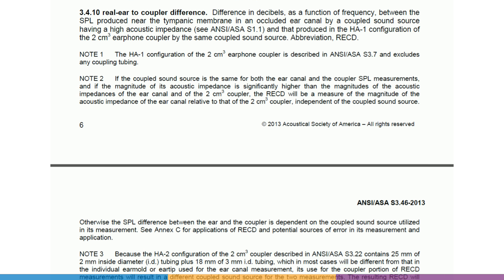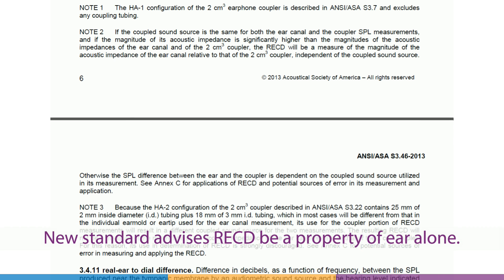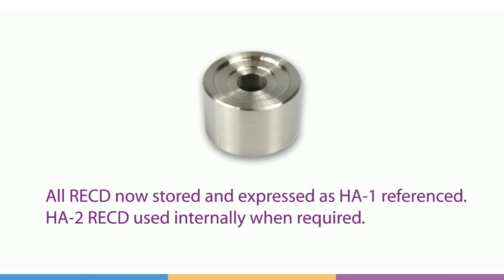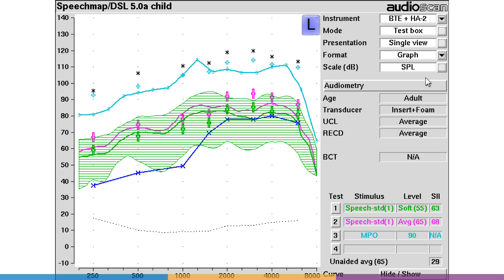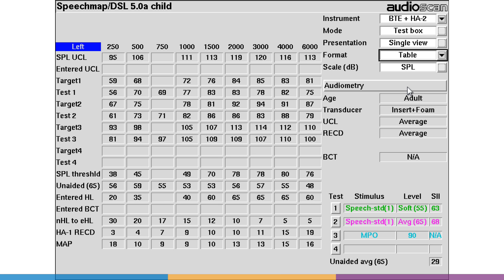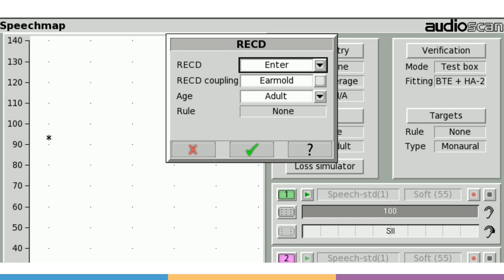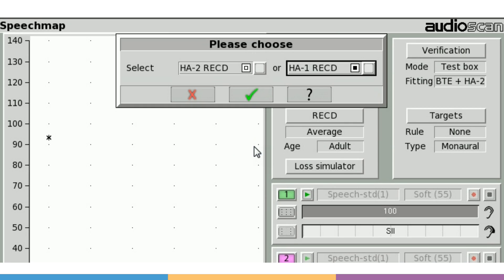The ANSI S3.46-2013 standard advises that the RECD should be a property of the ear alone and not dependent on the sound source and coupling method. To this end, an HA1-referenced RECD is preferable. On Axiom, RM500SL, and Legacy Verifit VF1, measured RECDs are expressed as HA1-referenced. This will be labeled as such on printouts and when storing in NOAH. When entering previously measured values, the coupler reference will be prompted for. Choose HA1 when the RECD was measured on current software or on Verifit 2; choose HA2 if measured on legacy software.